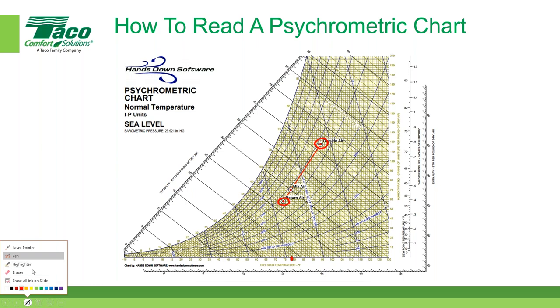Whenever I have the outside air and the return air pointed out here, all I have to do with the mix air temperature, which we said was about 79 degrees, is draw a vertical line, and where it intersects that diagonal line, that's the characteristics of my mix air. Mix air calculations are very important because in all HVAC systems, you always have some part of the system where you're mixing two streams of air.